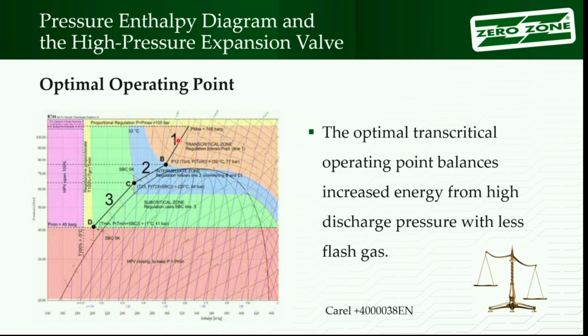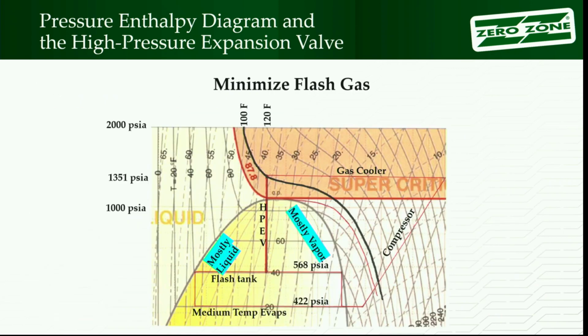On the other side, I'm going to get a lot more cooling effect out of the refrigerant I am circulating. So that's a win. So that software is taking a look at it, and it's making a decision and saying, for the leaving temperature out of the gas cooler, this is the optimum operating pressure for your system to get the most efficiency out of it. So I mentioned a couple of times now the leaving temperature of the gas cooler, right? We're looking at that. So it turns out of all the different sensors you have on a system, that's probably one of the most important ones that you really want to make sure is well attached, well insulated on it.